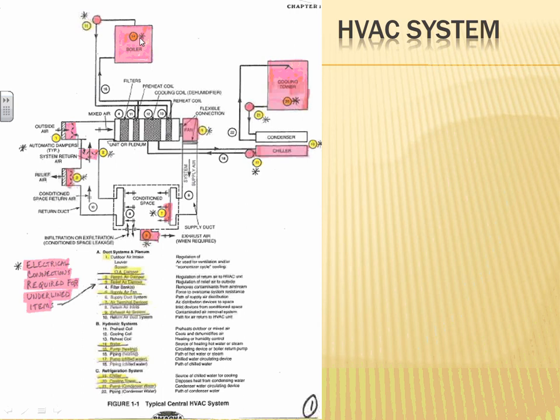I also need some type of control circuit and power circuit to control and power that gas boiler. It's not an electrical boiler, though it could be an electrical boiler too. Then I have the fans, these big fans sitting inside the air handling unit and throwing air into multiple coils. If it throws the air into the hot coil, it gets heat from this side. Throw it in the cold coil, it gets cold from the other side. I'm simplifying it here. And then there are a couple of dampers here that you have to pay attention to, where air exchanges between the outside and recycling and so forth. A couple of dampers that we either have to power or have to be aware that the mechanical contractors have to pick these up as part of their control or power points that they have to deal with.